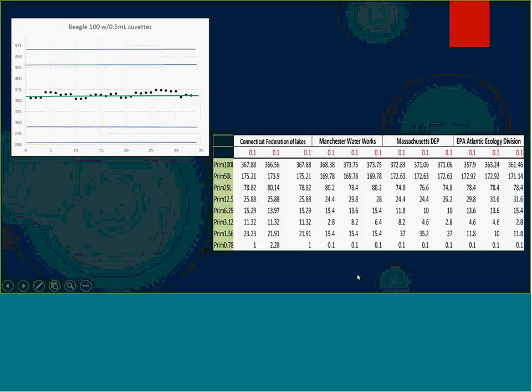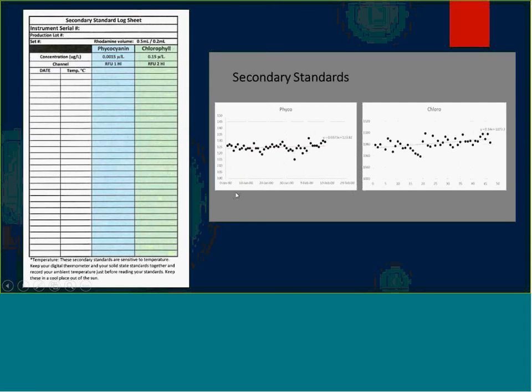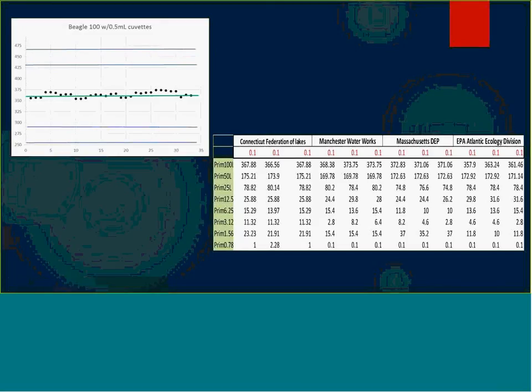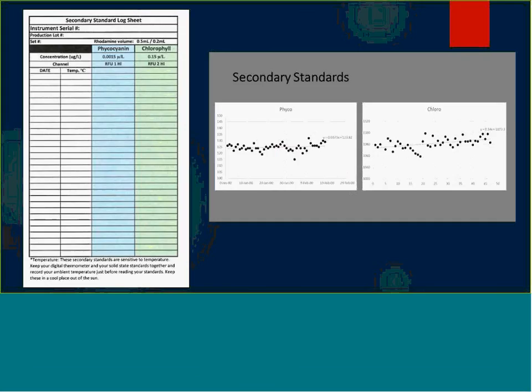We can then do standard control charts, looking at our calibrators, examining the variation across the mean of all the instruments between two and three standard deviations to see where instruments fall. We also run through a dilution series through the course of the calibration process to see where we start losing our ability to read the standard. The other QA element we employ is in the field: a secondary standard log sheet goes out with all instruments, so that every time they go out on a sampling day, they can record the temperature, look at the phycocyanin and chlorophyll, and track any changes in instrument readings and sensitivity through the sampling season.